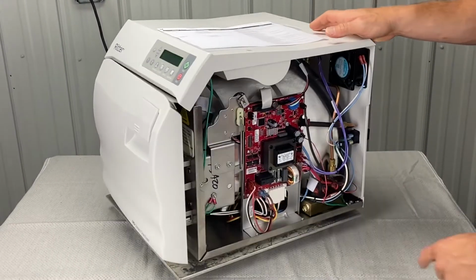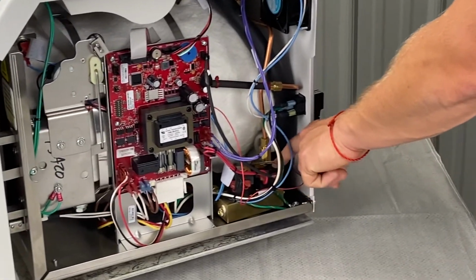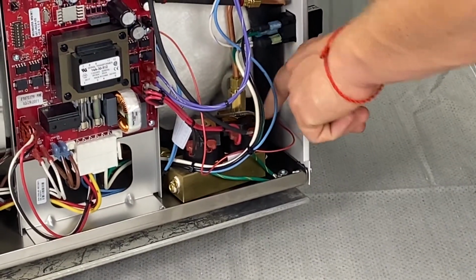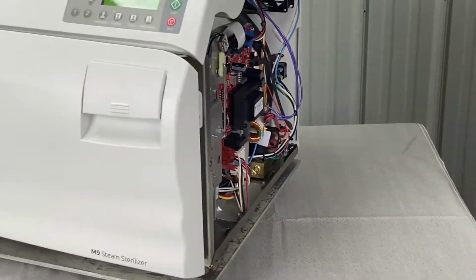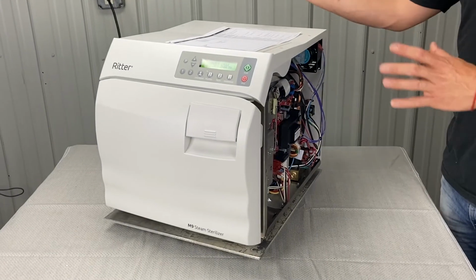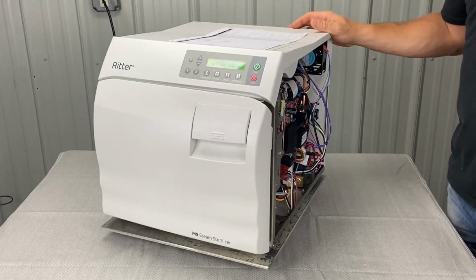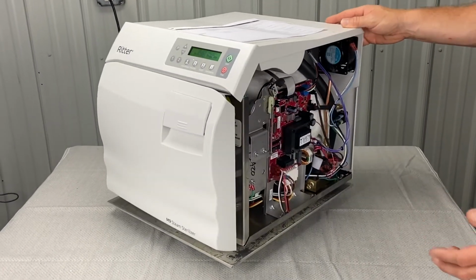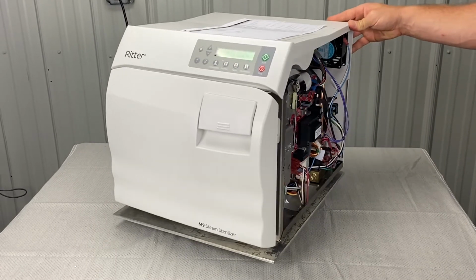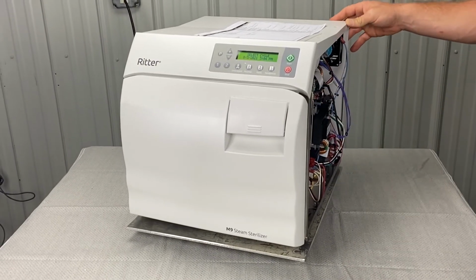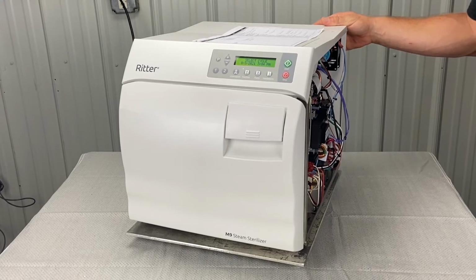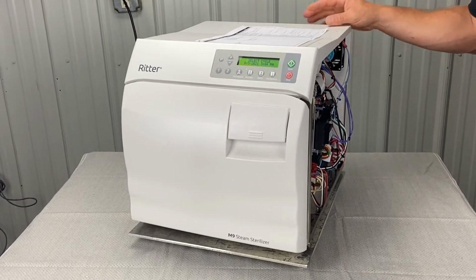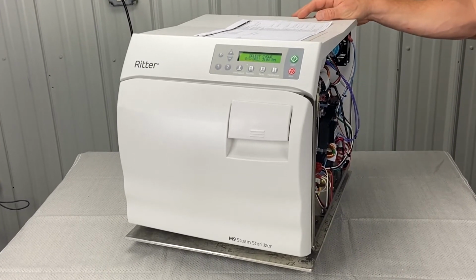Check for leaking or defective vent valve. This is the vent valve. Check for water leaking from condensation coil spout. That's again in here. With the top cover off and everything open, you can really see what's leaking and what's not. But again, you're gonna need some patience, a big open area, a couple tools. Not a huge deal. Check all plumbing fitting connections for leakage.